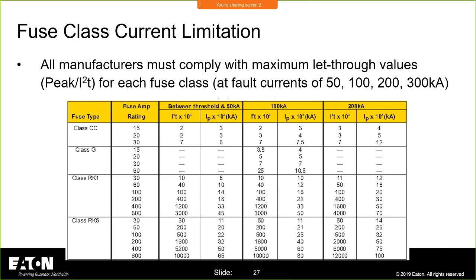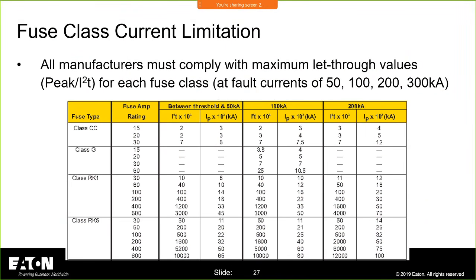And this is an example of the tables that are used at 50, 100, 200, and 300,000 amps. Yes, I did say 300,000 amps. Do you know we have fuses that can interrupt up to 300,000 amps? And you know what we had to do to make that possible? We had to build a lab big enough to be able to pump 300,000 amps through it.